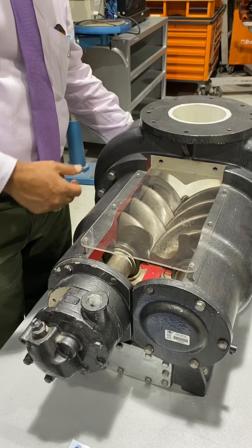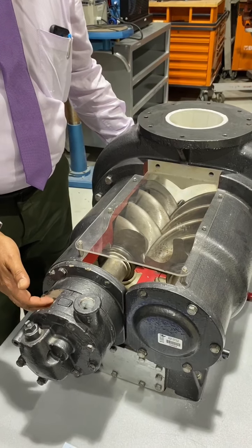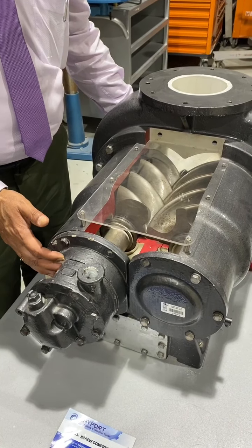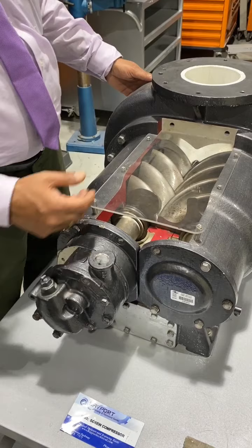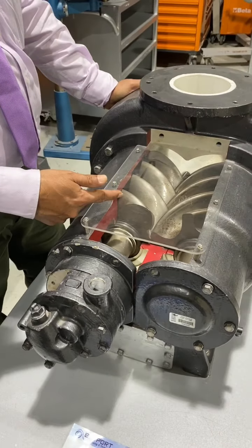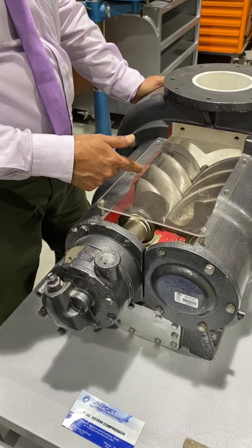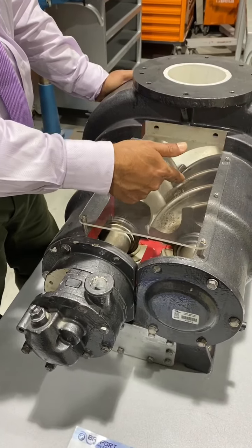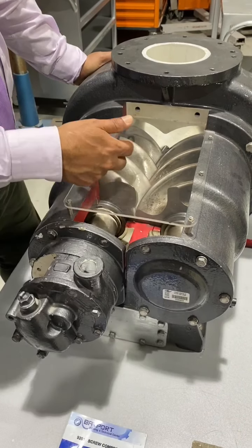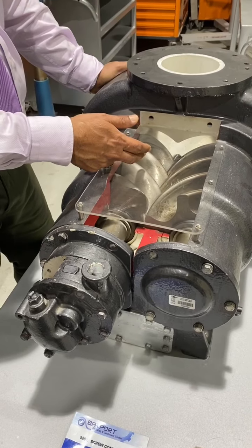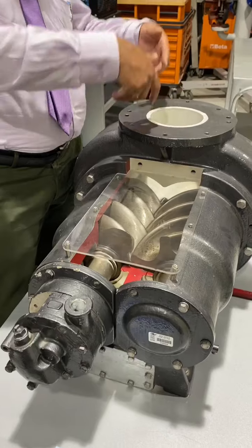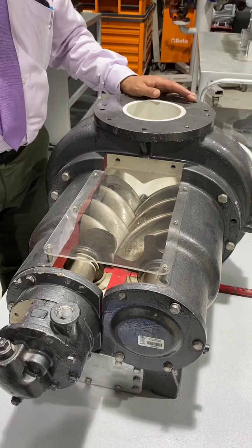So at both ends there will be bearings, and there will be seals also, a high pressure mechanical seal to prevent any leakage. And then there will be a driver here, an electric motor to drive the male screw, so that when the male screw rotates, automatically it will rotate the other, the female screw. At the same time air is sucked through the suction side and compressed between the gaps of the screws, and then the compressed air will discharge from the outlet to the tank or wherever you need. That is how it works.